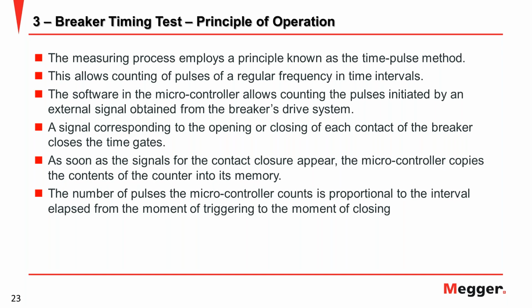Basically, in general, this testing measures how long the change of the resistance takes. When the breaker closes and opens, there is a change in the resistance value within certain limits. So this equipment wants to measure how long the changing process takes from value A to value B, because when open and closed, the resistance of the circuit changes. Because the change is very fast, you need a microcontroller and a high speed timer also. This is why you need special equipment to do this testing. We call it the breaker timing test.